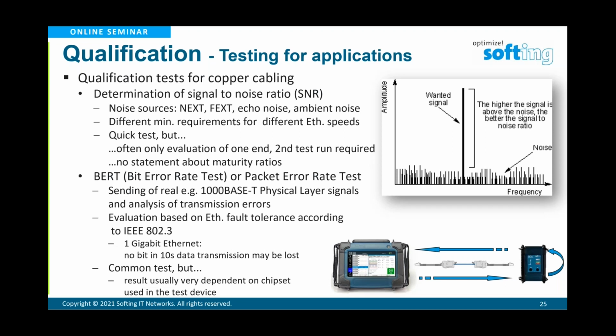The bit error rate test or packet error rate test is really sending 100 or 1000 or 10,000 base T over the physical layer. So we really have signals like you usually have in transmission at the end. That is basically what this unit is doing with a bit error rate test. And it is evaluating that against the Ethernet's fault tolerance according to IEEE 802.3. For 1 gigabit, for example, there is no allowance for any bit loss inside of 10 seconds. That is a common test, but this test is also very much dependent on the chipsets that are used in the test device.